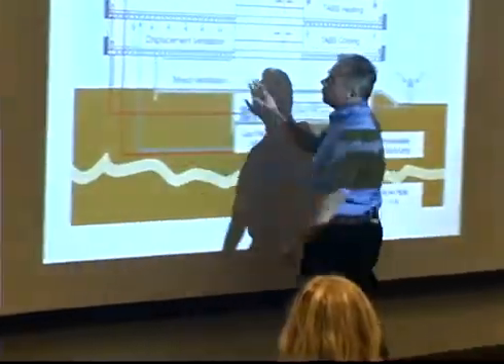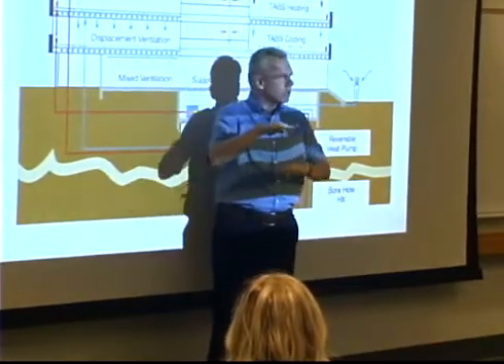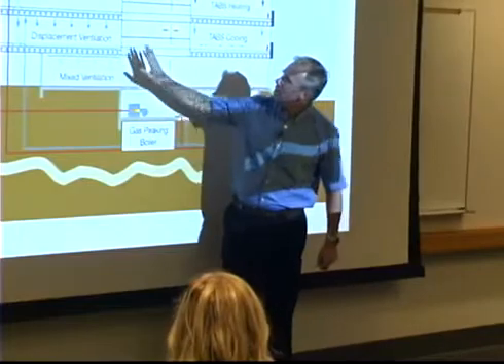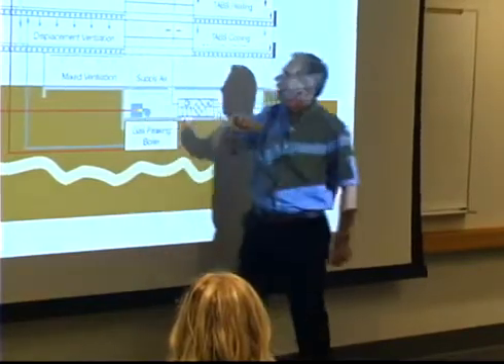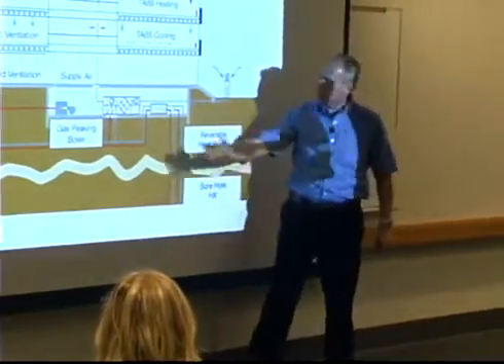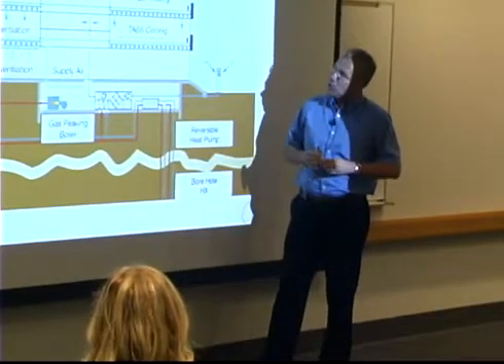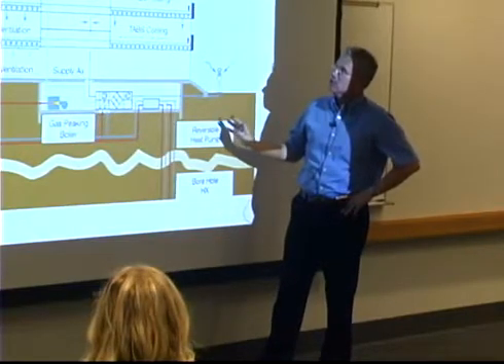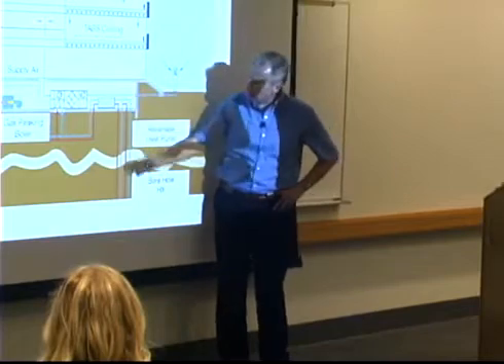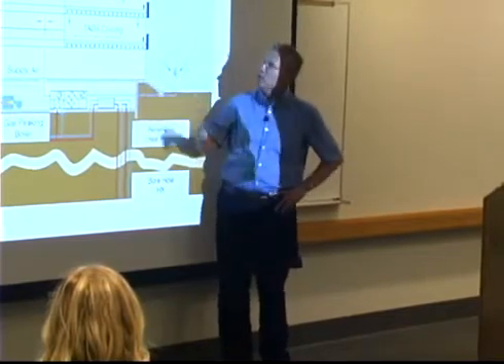The ventilation air is provided through a displacement ventilation system. So you see the air coming in here and being delivered through the floor, either a raised floor arrangement or diffusers on the side. So you have small amounts of air. These are just the ventilation air. This floor may be cooling, this floor may be heating. This is just an example. The return air is collected here and then conditioned again in this dedicated outdoor air system. The peaking boiler may be necessary just to make sure that if the heat pump doesn't have enough capacity, you can deal with that. So a separation of building and ventilation loads, a reliance on massive construction, the inclusion of environmental heat sources and sinks, in particular the ground where possible. All these things combined with high performance envelopes allow for a good performance of these buildings.